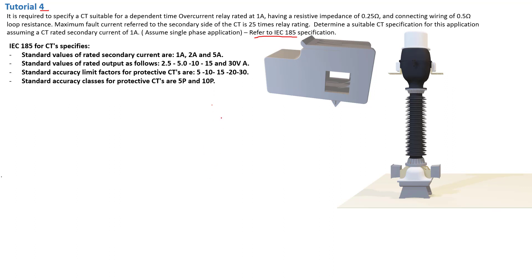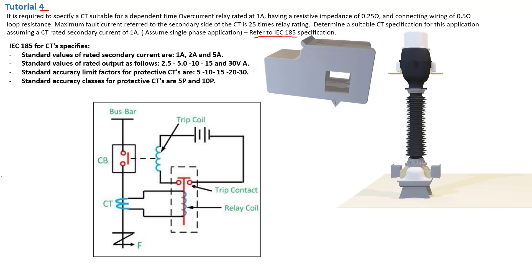What happens when the current transformer reaches saturation? It becomes useless. If it reaches saturation, it will never tell you how much current is flowing — it could be 100,000 amps and it will never have a proportional current at its secondary. That's why it becomes useless. And hopefully, before it reaches saturation, your circuit breakers have already tripped and isolated the fault.